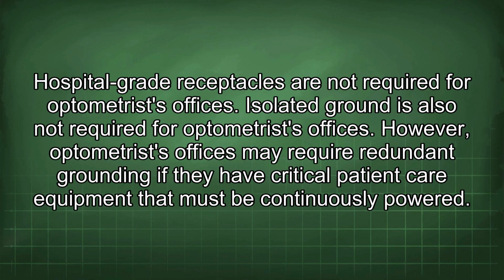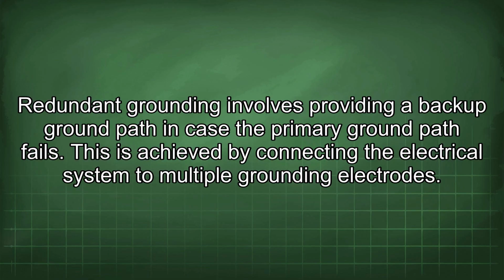Hospital-grade receptacles are not required for optometrist offices. Isolated ground is also not required for optometrist offices. However, optometrist offices may require redundant grounding if they have critical patient care equipment that must be continuously powered. Redundant grounding involves providing a backup ground path in case the primary ground path fails. This is achieved by connecting the electrical system to multiple grounding electrodes.